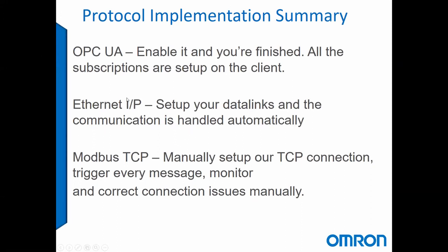Same with Ethernet IP. We are fully compliant. There's a bit more setup involved. Obviously, you need your data links. You may need an EDS file if it's something third party. And the sequencing and everything is handled behind the scenes, at least for implicit messaging. Explicit messaging, far less common, and it would be comparable to what we did with Modbus there.